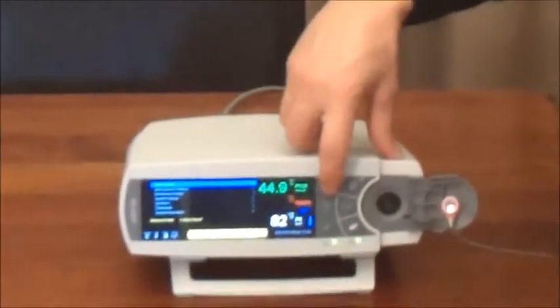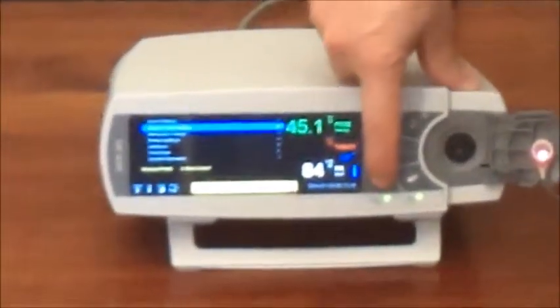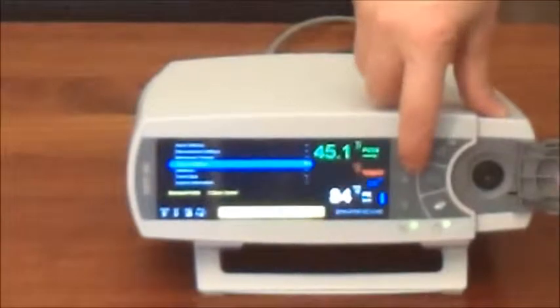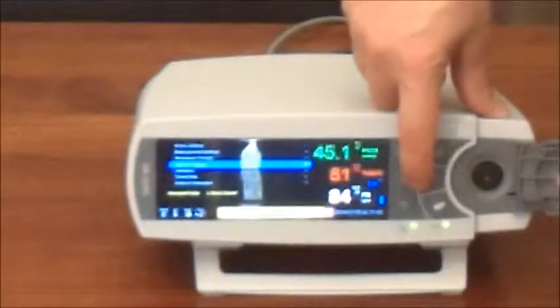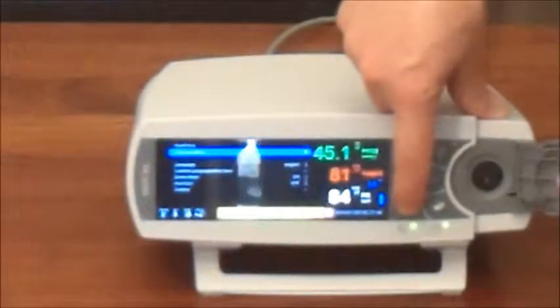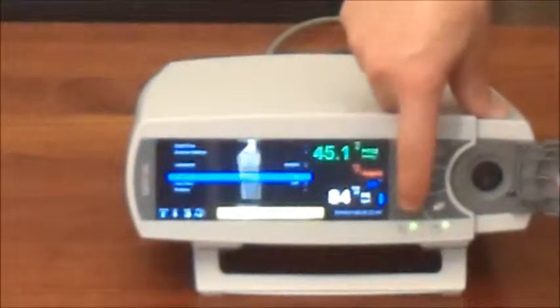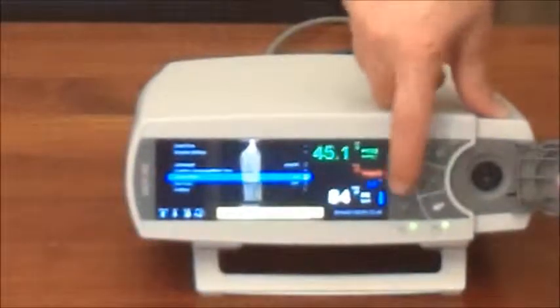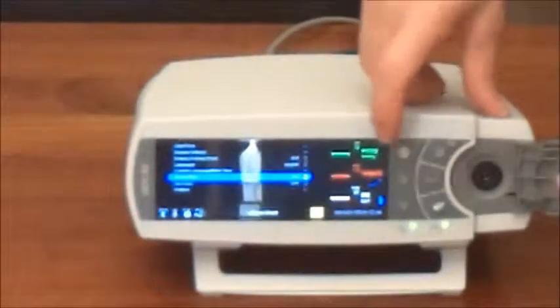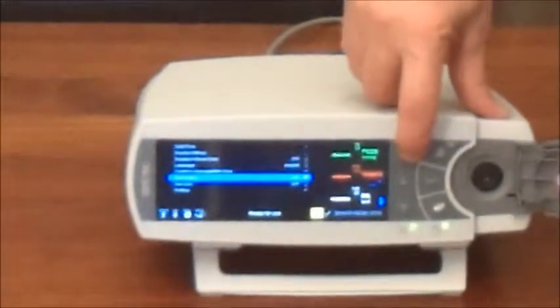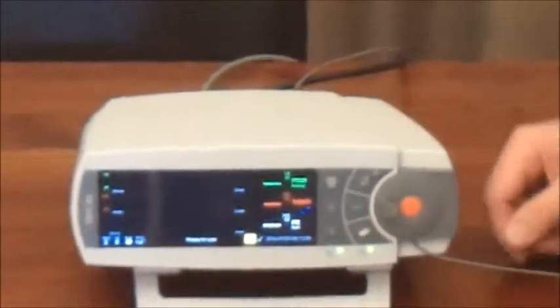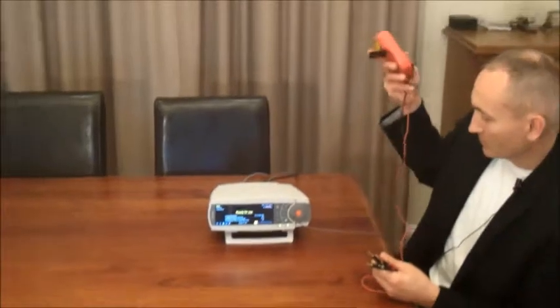Once we've done that, we can go back and take it out of demo mode because obviously we don't want to be confusing the night staff with demo mode. So we go to system settings, down to demo mode, enter, turn that off, go back through the menu. Now we close the door; it's ready for use, ready to go. I hope you found that informative. Thank you very much for viewing the video and I'll look forward to the next video.